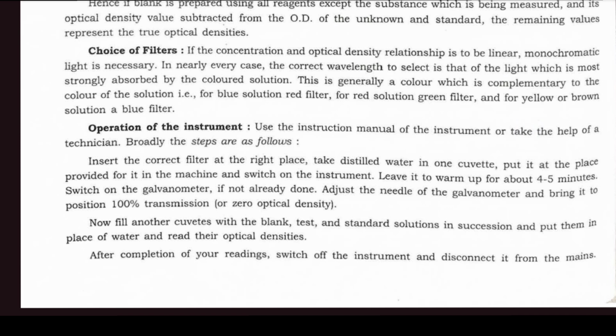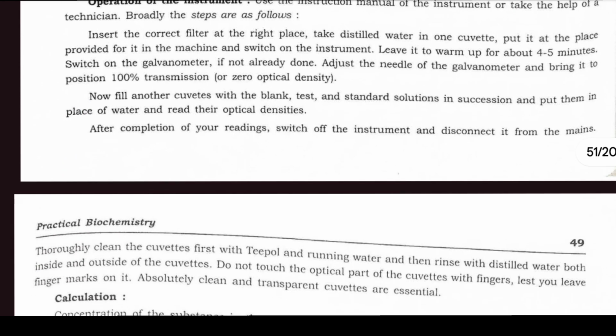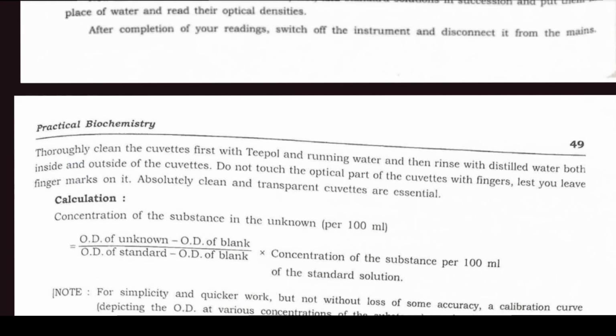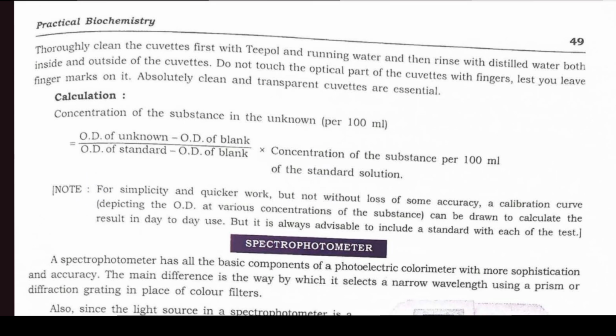After completion of your reading, switch off the instrument and disconnect it from the mains. Thoroughly clean the cuvette first with detergent and running water and then rinse with distilled water, both inside and outside of the cuvette. Do not touch the optical part of the cuvette with fingers lest you have finger marks on it. Absolutely clean and transparent cuvettes are essential.